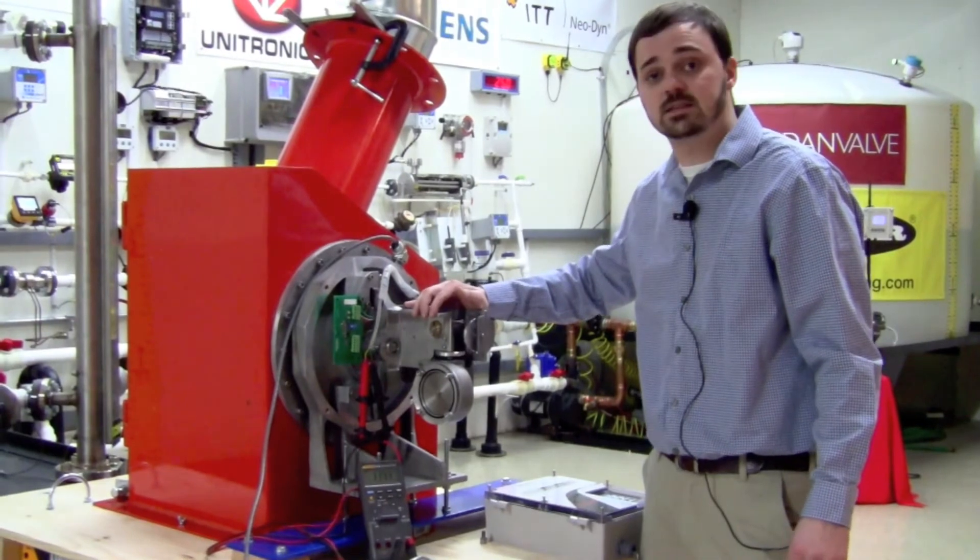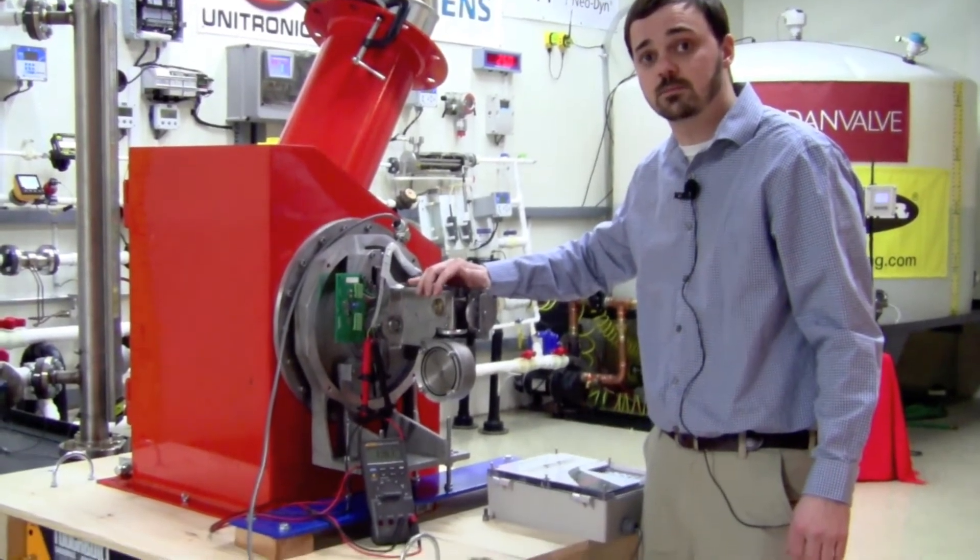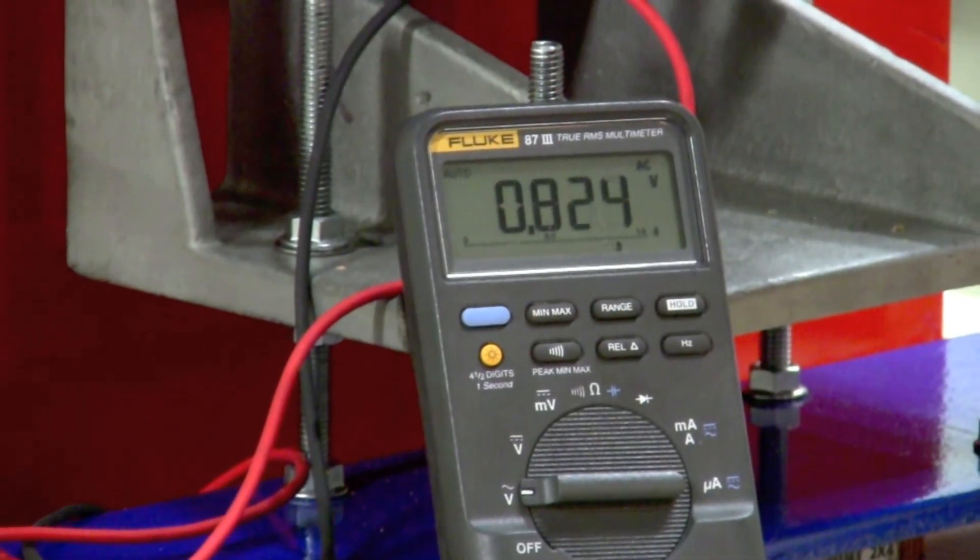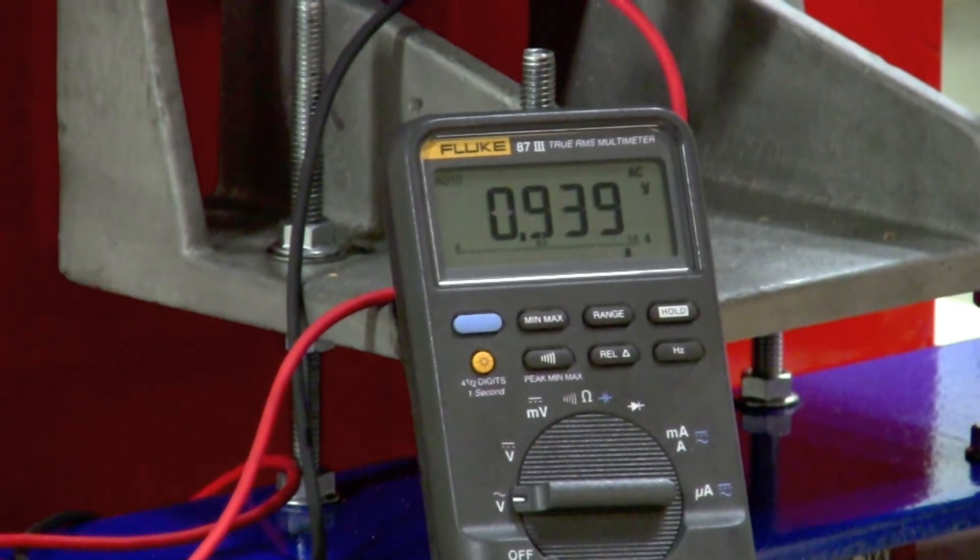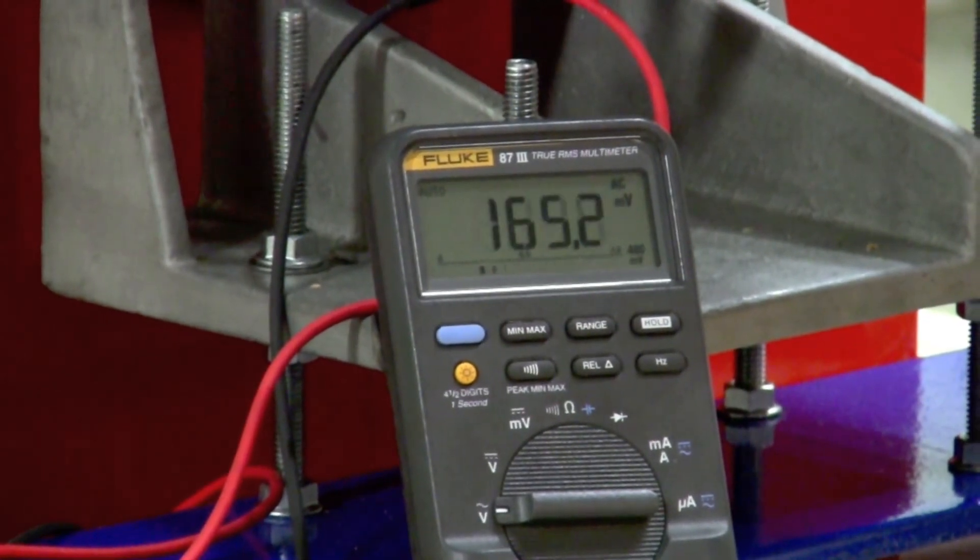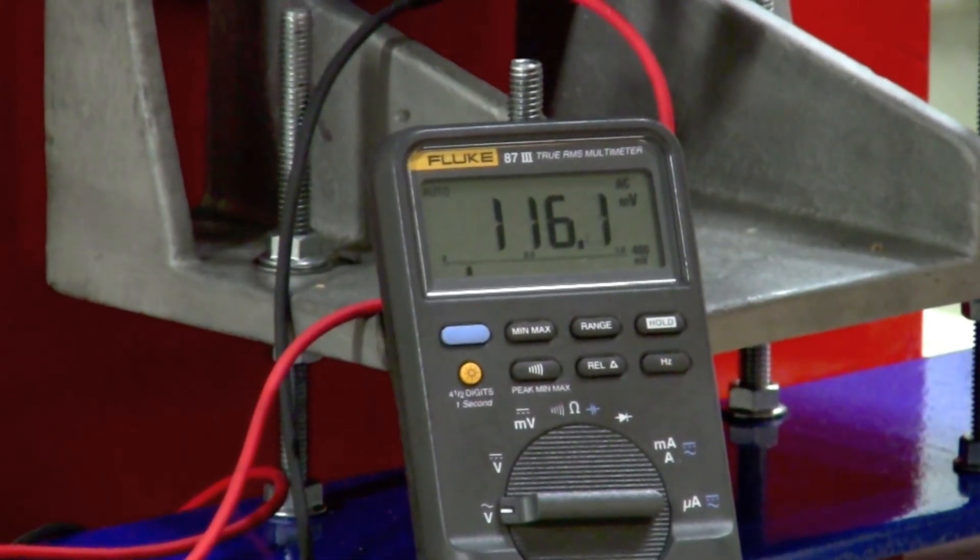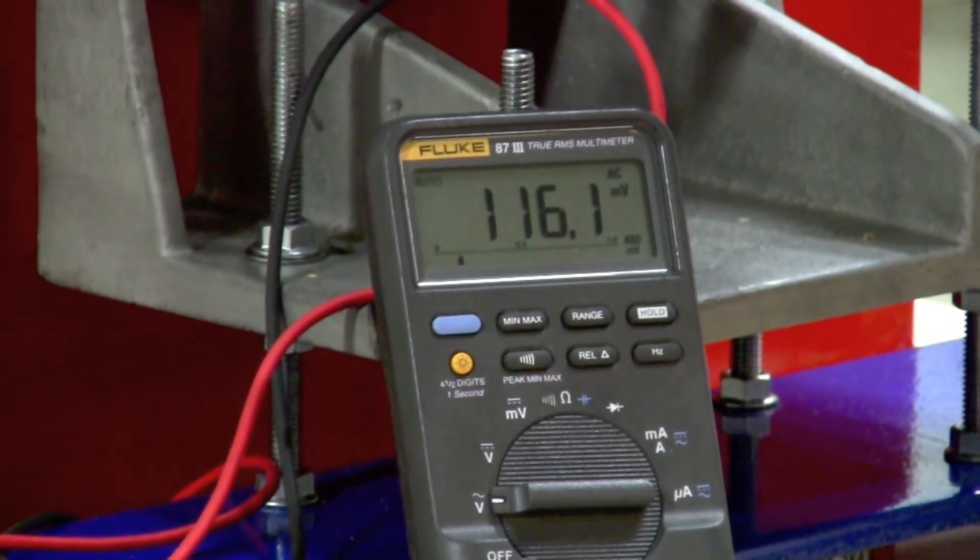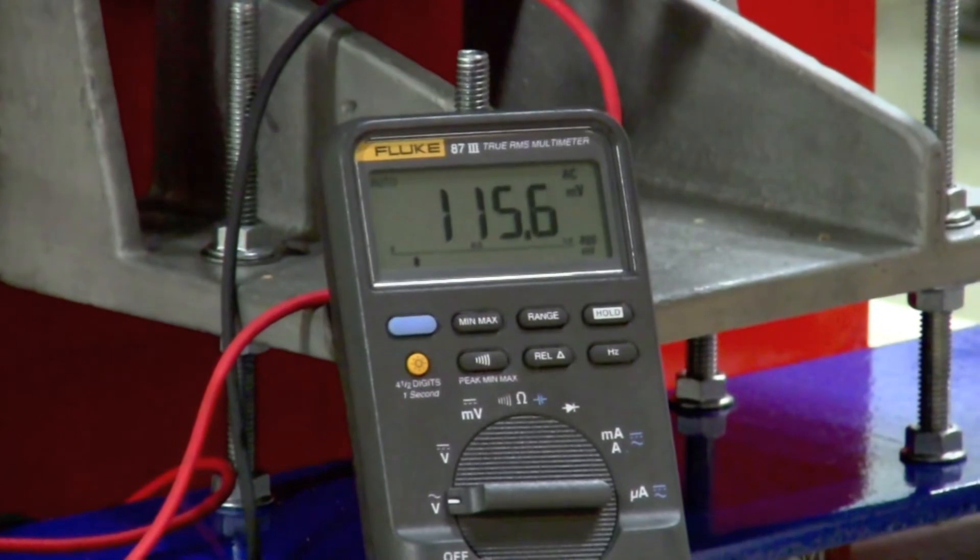If we squeeze the sensing head, we'll be able to see this demonstrated. Notice that it returned back to the zero position. With that being said, this sensing head is spanned correctly.